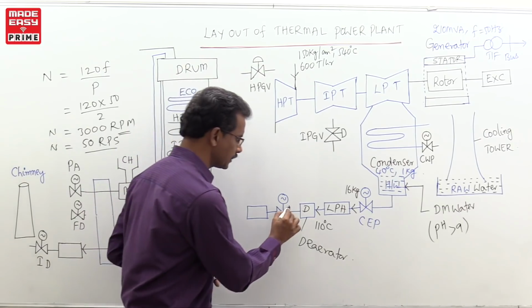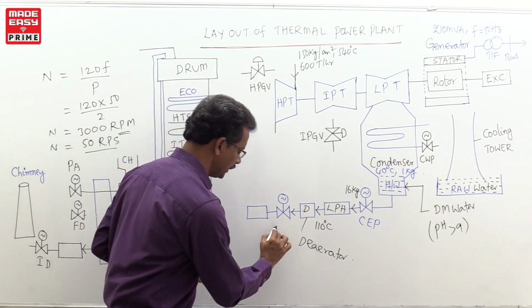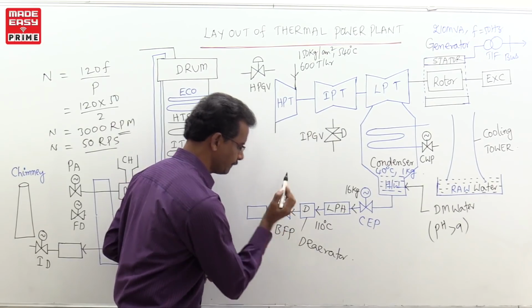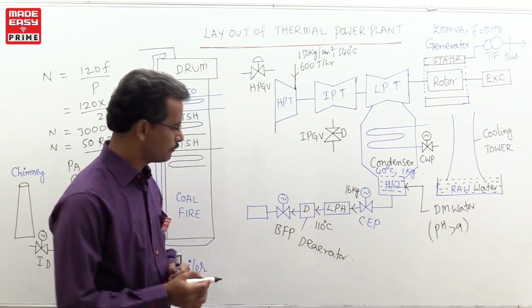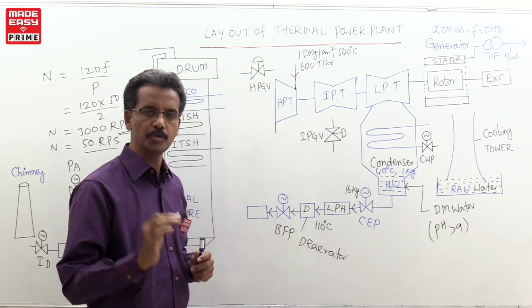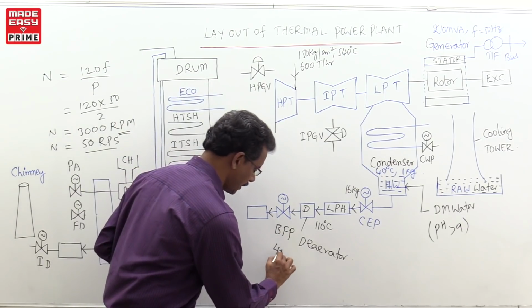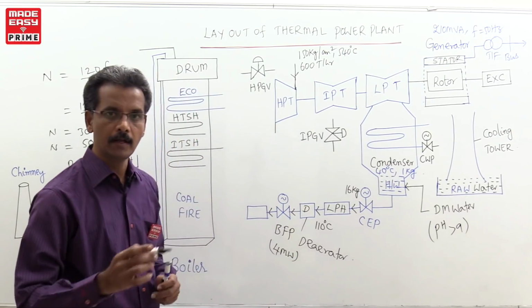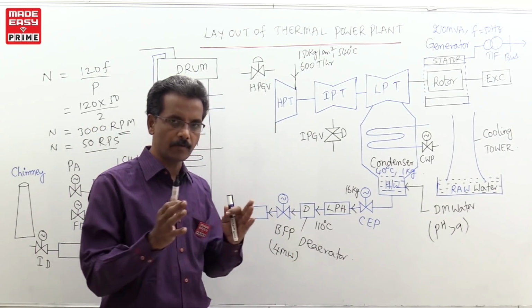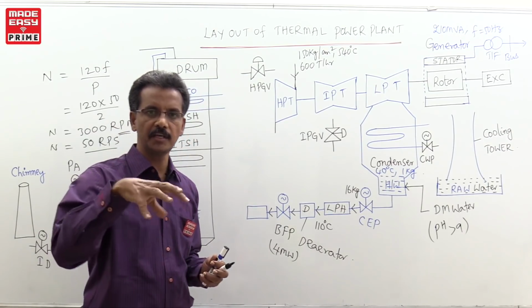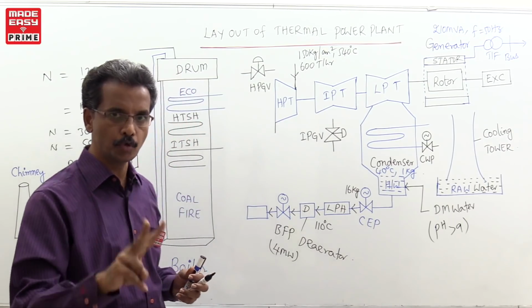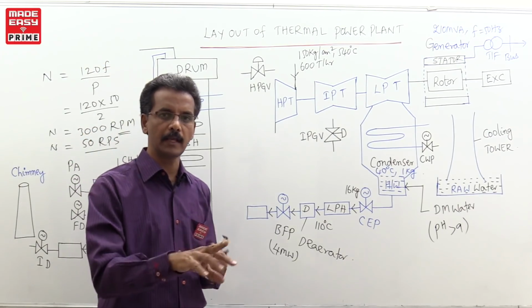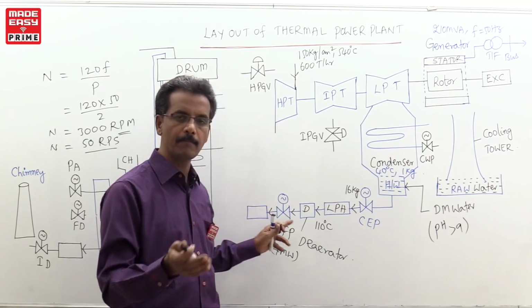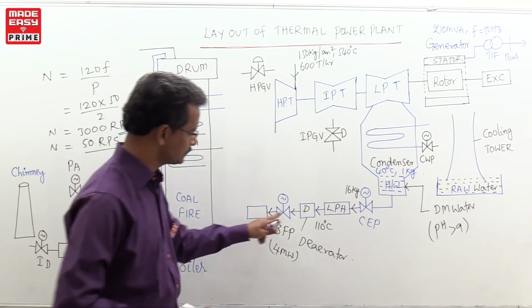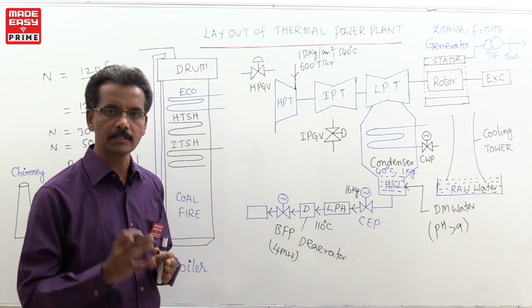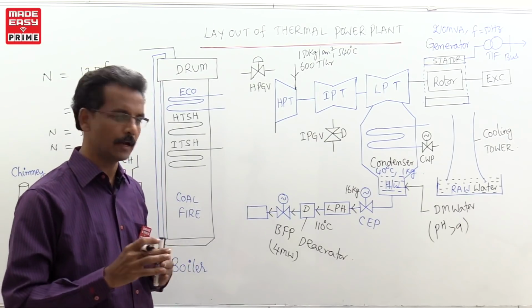Now, after this deaerator, water is sent to one of the important pumps. This is called the boiler feed pump. This boiler feed pump is the highest power consuming pump in the thermal plant. It will consume around 4 megawatts of electrical power. Generally, 3 pumps exist in the plant. Out of these 3 pumps, 2 are running and one is standby. If one of the working pumps fails, then the standby pump is taken into consideration. So, this boiler feed pump has around 4 megawatts of power consumption each, a total of 8 megawatts generally.